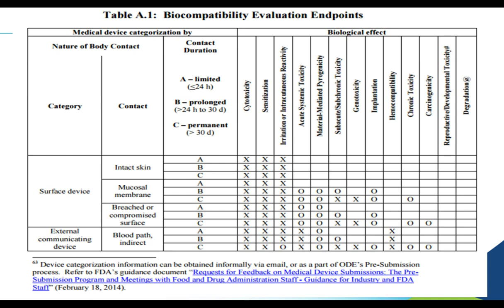I want to start off with just talking about Table A1, or Table A, in ISO 10993-1. This is also the exact table from the FDA guidance document, which is available online. This is their guidance document for biocompatibility testing and how the FDA interprets the requirements. I just want to point out where we're led to do irritation testing. First, we talk about what kind of device we have and how it contacts the body, and we start very generally with, is this a surface device or is this an implant? Then we move to a more specific location within the body as we try to identify where the risks are for the patient contact. And then we isolate the time duration.